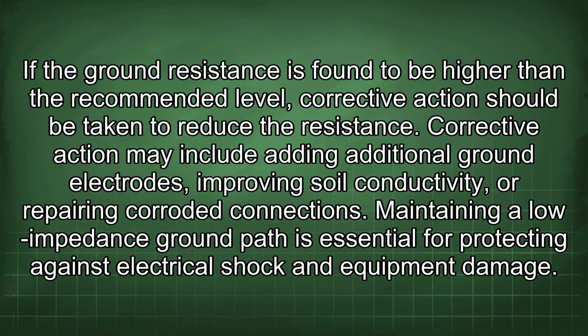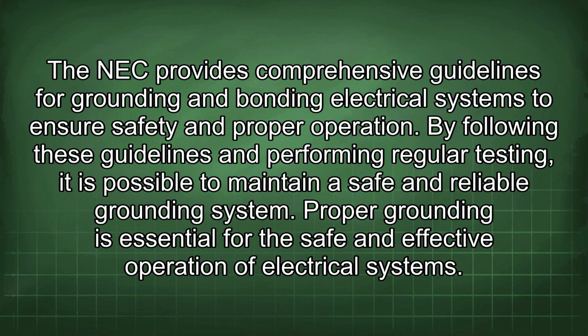If the ground resistance is found to be higher than the recommended level, corrective action should be taken to reduce the resistance. Corrective action may include adding additional ground electrodes, improving soil conductivity, or repairing corroded connections. Maintaining a low-impedance ground path is essential for protecting against electrical shock and equipment damage. The NEC provides comprehensive guidelines for grounding and bonding electrical systems to ensure safety and proper operation. By following these guidelines and performing regular testing, it is possible to maintain a safe and reliable grounding system.